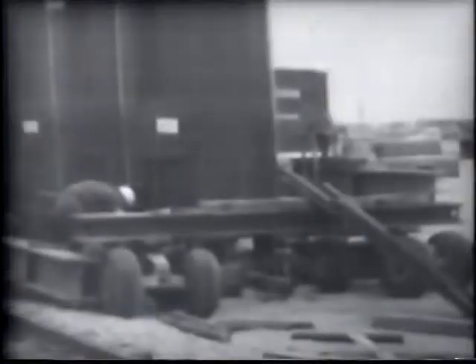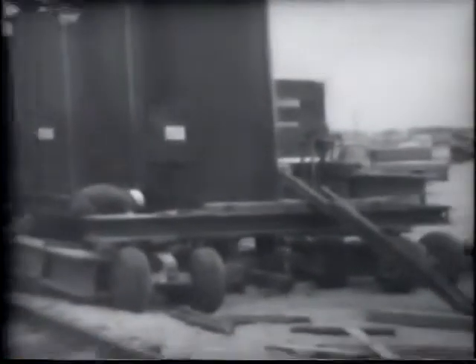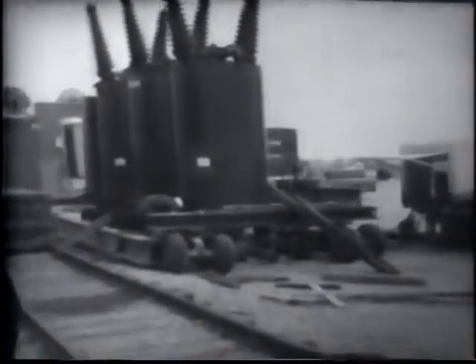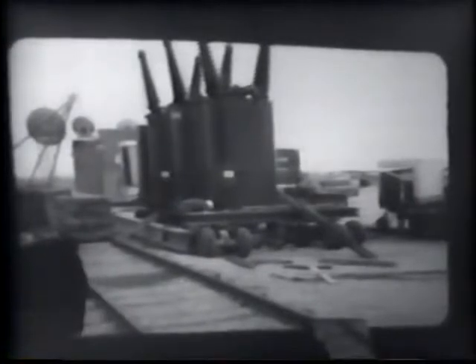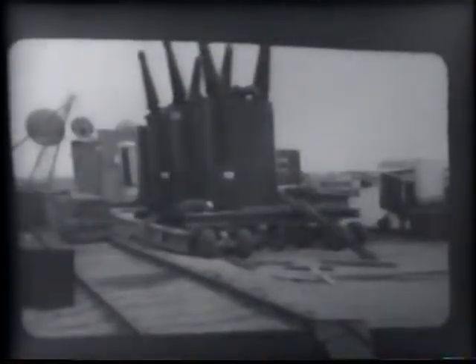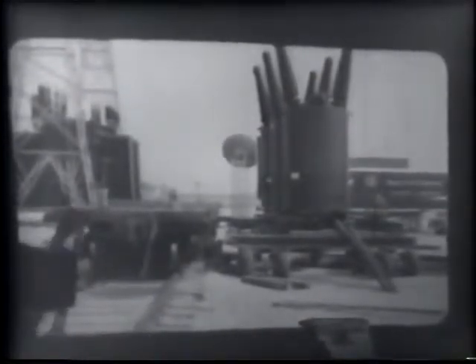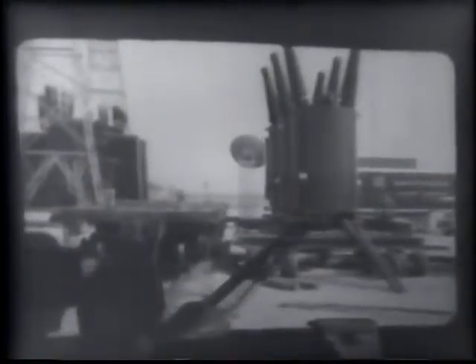Now, the next group of breakers are some 161 kV breakers that we don't have as much detail on, and we'll go through them fairly rapidly because we may want to come back to them at a later date during our discussion of breaker installation. This is just a view of the type of foundation used for a 161 kV circuit breaker. This is the 3-tank 161 kV circuit breaker. The porcelain bushing, there again you notice the tremendous difference in size. It's being loaded on this multi-wheel dolly to be moved from the railroad car to its foundation. And this shows the railroad car that it was shipped on, and then it was moved over there. All 3 tanks are mounted on 2 steel I-beams.